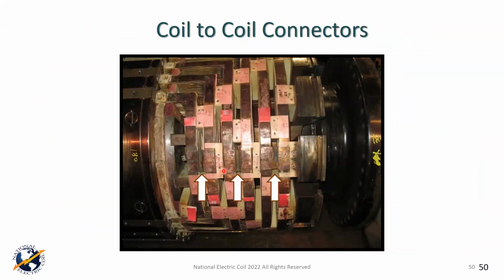Now, we talked about the coil-to-coil connectors. This is just a better picture showing it to you. Now, I'd like to ask you, how is this retaining ring put on? Do we see a fit up here? No, that's actually the end blocks. The fit is back here. So we know this is spindle mounted, and you've all been educated on the potential for top turn cracking if you have a spindle mounted unit, so keep that in mind.